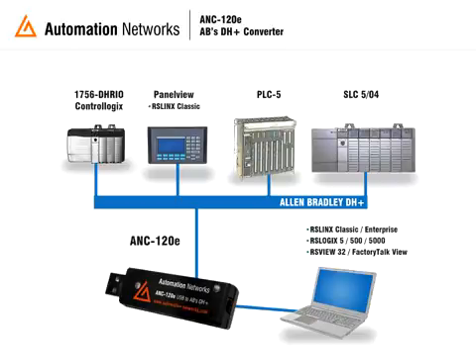Another great feature of the ANC120E is its auto-configuration capabilities for DH+ node, baud rate, and cable polarity. By default, the ANC120E will automatically scan the DH+ network to find a free node number and the baud rate to configure itself for a successful DH+ connection. Of course, you can configure a fixed node number and baud rate if you prefer. Automatic polarity detection allows connecting the DH+ cable without worrying about correct polarity, allowing simple usage without the need to reconfigure the device each time.